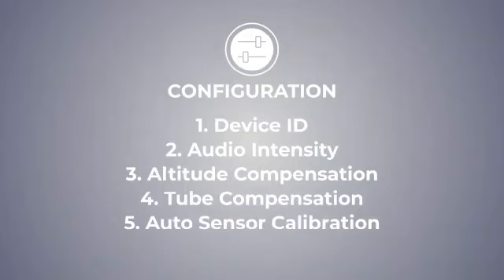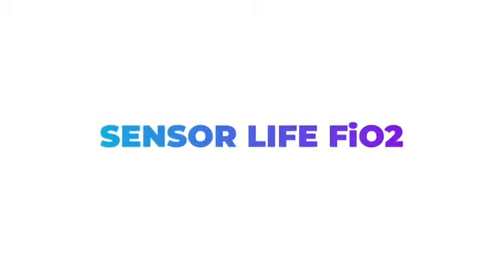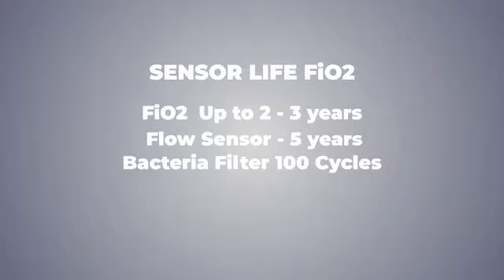Sensor life: The FiO2 sensor is quite durable with an expected shelf life of 2 to 3 years depending on the use, while the flow sensor has a durability of 5 years, and bacteria filter is effective till 100 cycles.